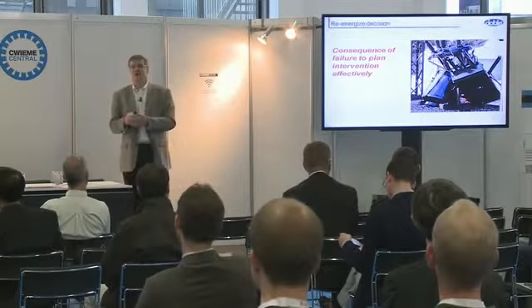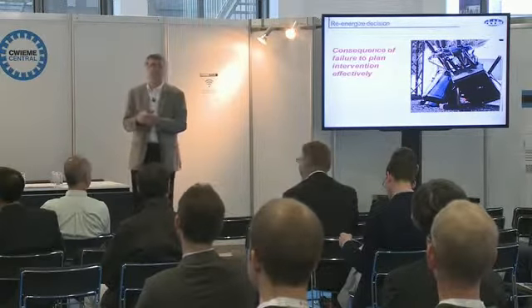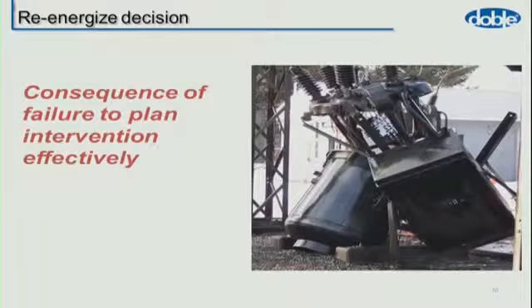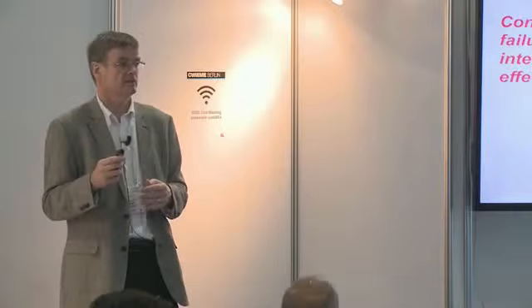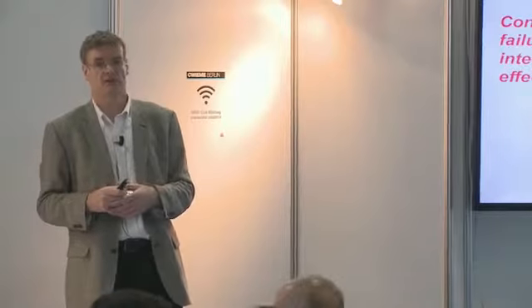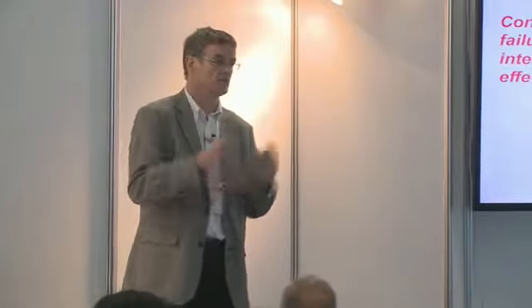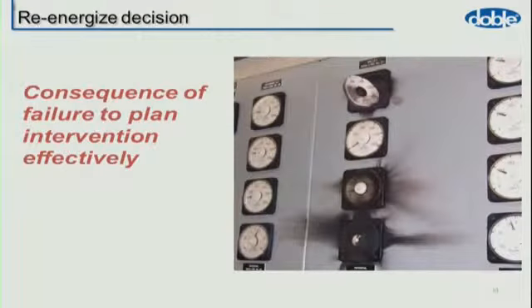What's wrong with this circuit breaker? This circuit breaker would have been in slightly better condition if someone hadn't tried to re-energize it after it had failed. This may seem like a ridiculously small thing. There's a control room, they're looking to see if they can re-energize a breaker. They're told it's okay, R210 can go back in, they switch it in. The wrong people have been looking at this. That put 11 kV back on the control wires, sent the energy back into the control room, burst all of the controls, and you've got flying glass across the control room.